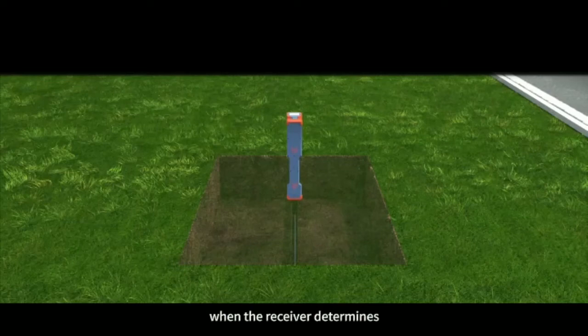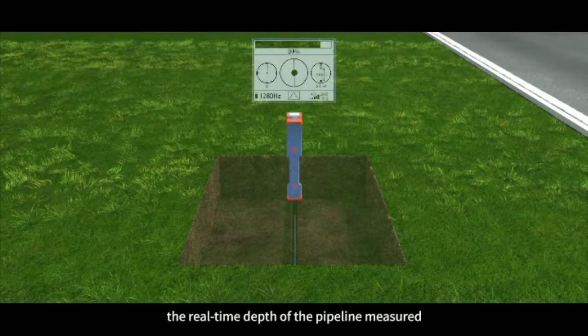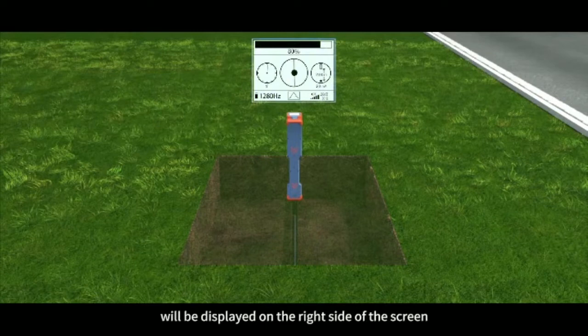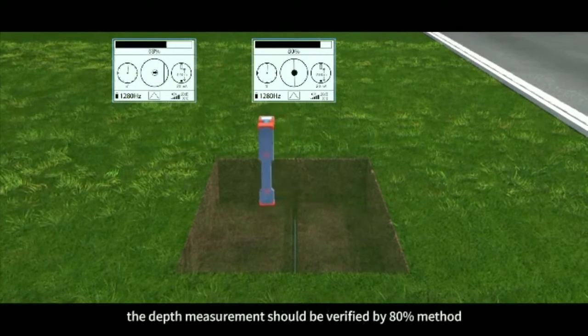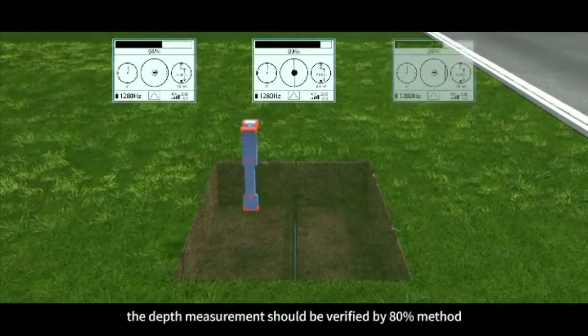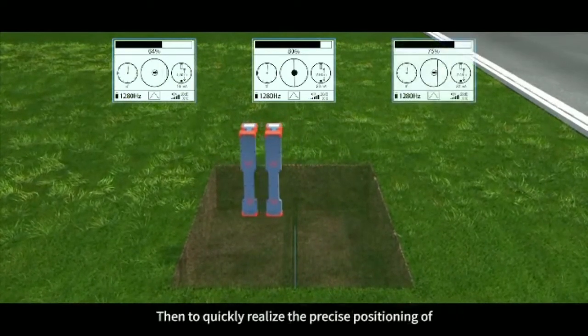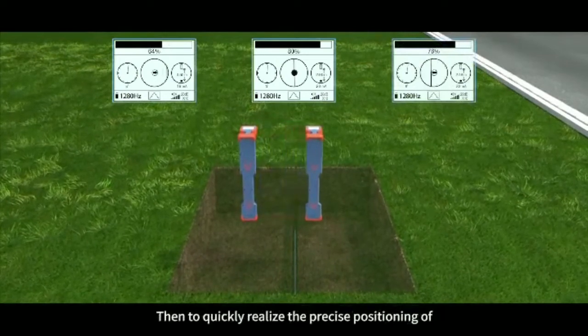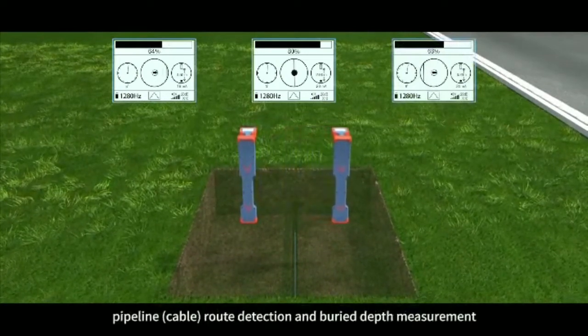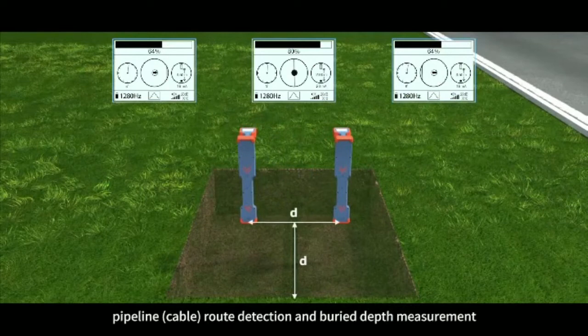When the receiver determines that it is basically above the pipeline, the real-time depth of the pipeline measured will be displayed on the right side of the screen. When the pipeline is deep, the depth measurement should be verified by the 80% method. Then you can quickly realize the precise positioning of the pipeline, cable route detection and buried depth measurement.